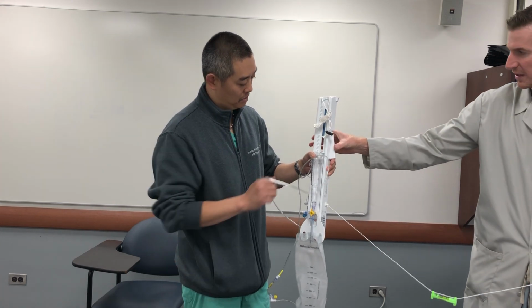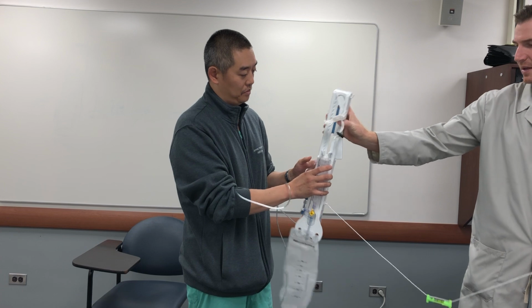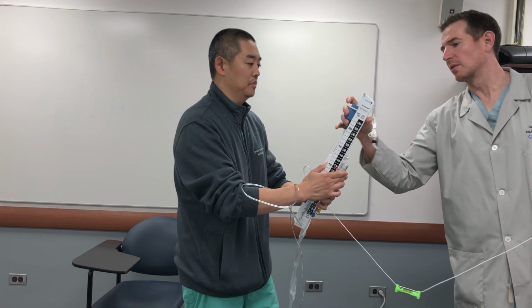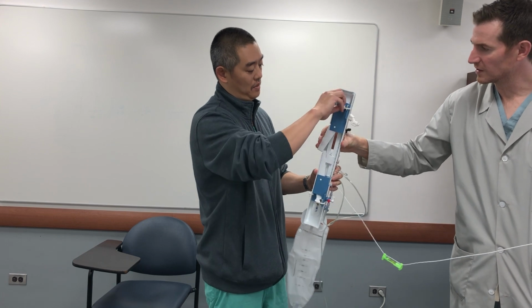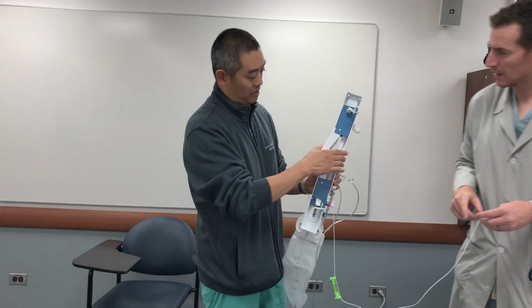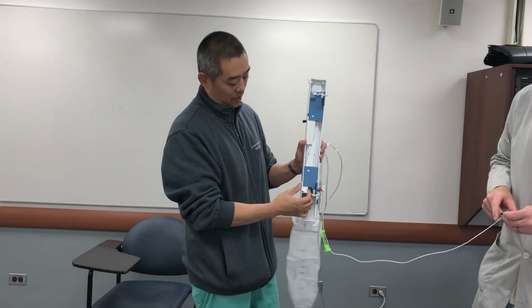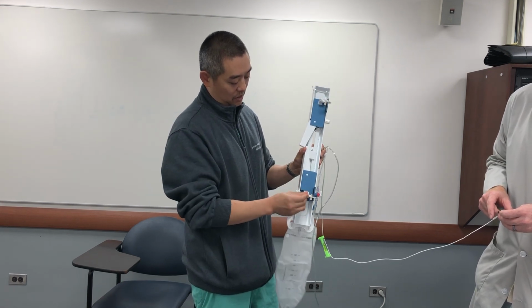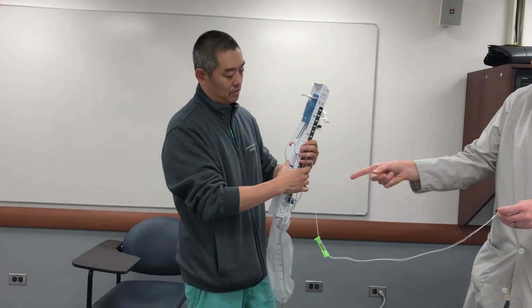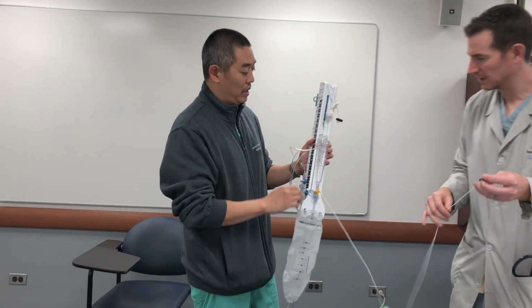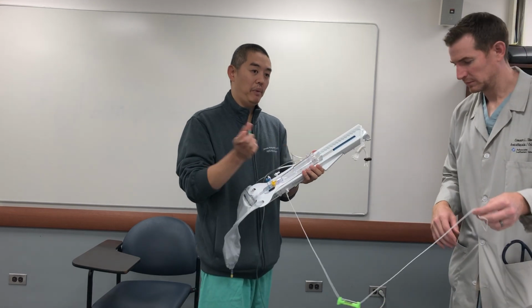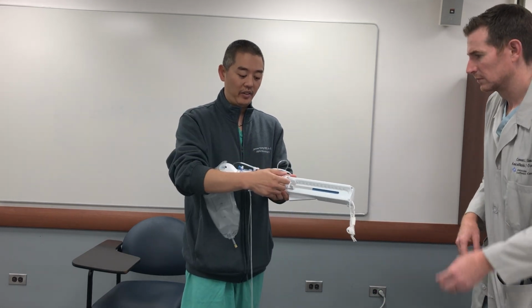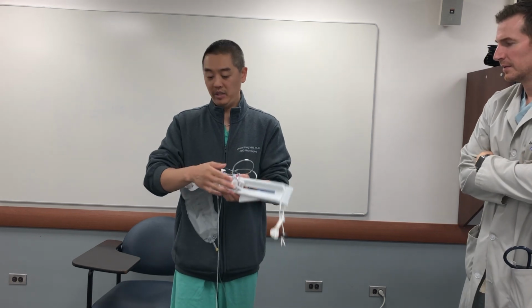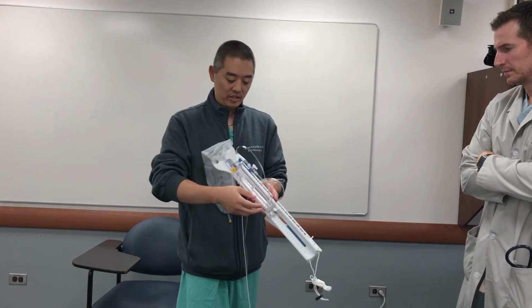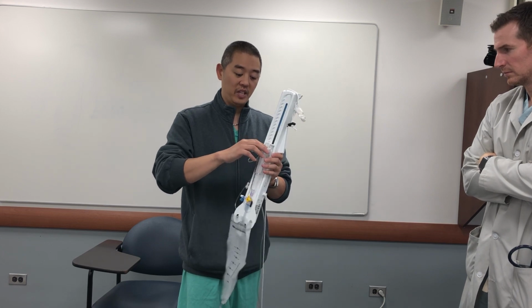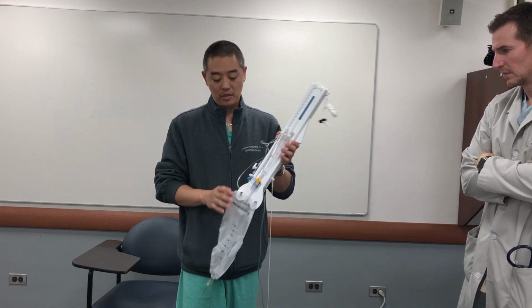There are these little clamps on the back, which a lot of times they'll have set in the bed. You squeeze these little tabs, and there's kind of belts and suspenders: the clamp that goes around the IV pole, and then a strap that goes around as well. You put it on the pole; you don't want to just have it lying in their bed. This is nice because with the old Becker system, if you laid it flat and the air valve got wet, you would have to change the whole system. With this one, if it gets wet, you don't have to change the whole system. It's fine, so don't worry about that.